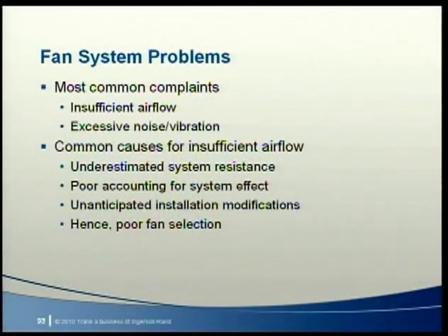Dennis, are there any common fan problems that you hear about? Well, sure, but hopefully with all the fan selection information we've covered so far, most fan system problems can be avoided. Once installed and commissioned, air handlers usually meet or exceed expectations, but sometimes they don't. The most common fan problems that we hear about are less than expected airflow and more than expected noise. Dave will discuss noise-related problems in a minute, so I'll talk about insufficient airflow.